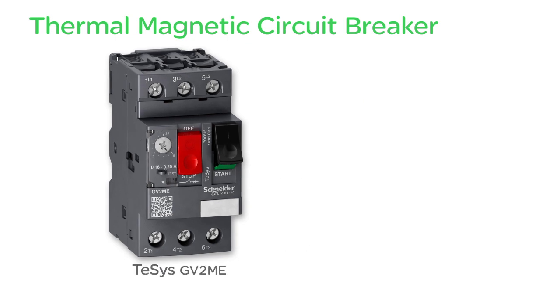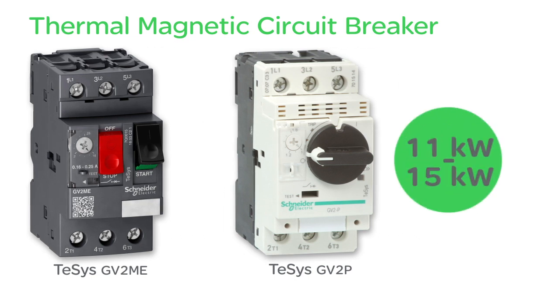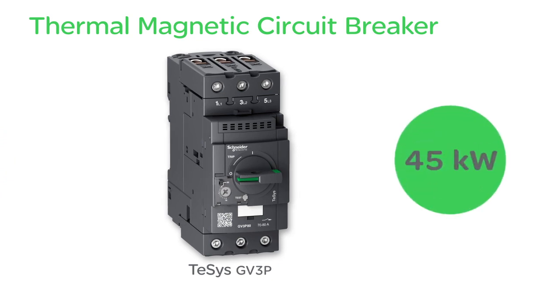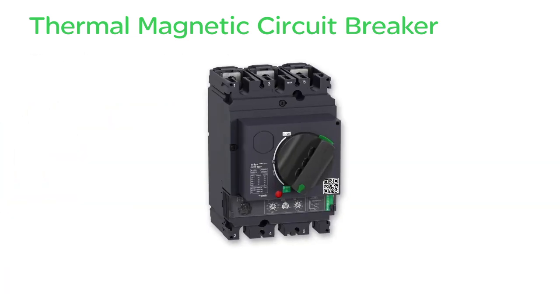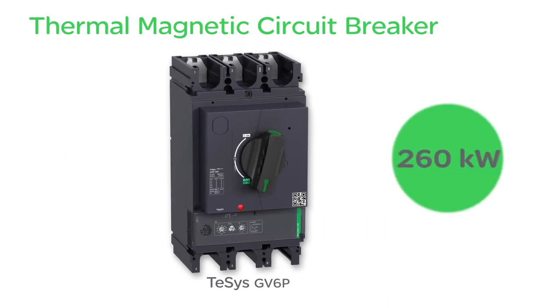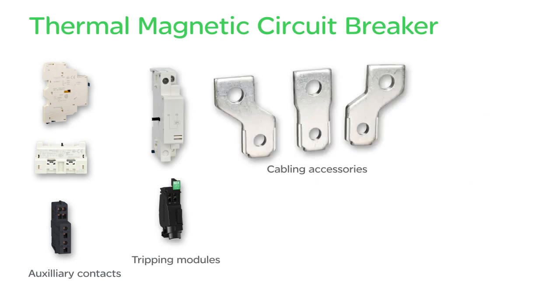The magnetothermal circuit breaker is an alternative solution for overload protection and can be combined with short-circuit protection. GV2ME and GV2P circuit breakers cover up to 11 and 15 kilowatts, GV3P up to 45 kilowatts, GV4P and GV4PE up to 55 kilowatts, GV5P up to 110 kilowatts, and GV6P up to 260 kilowatts. These circuit breakers can also be equipped with the TeSys GV range of accessories.